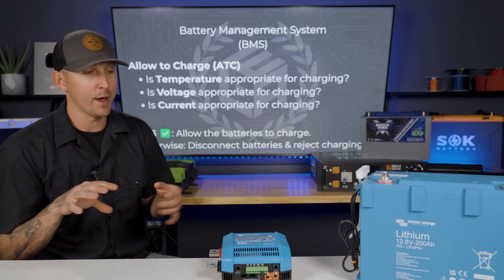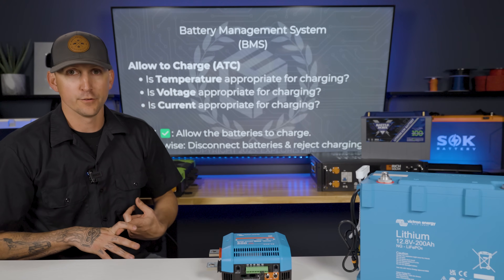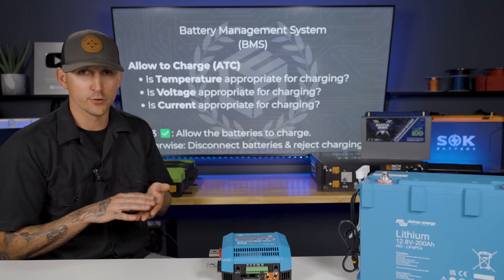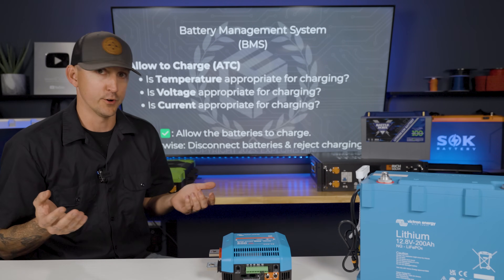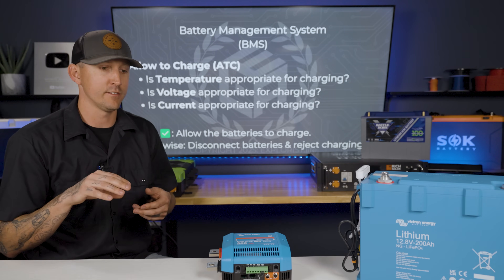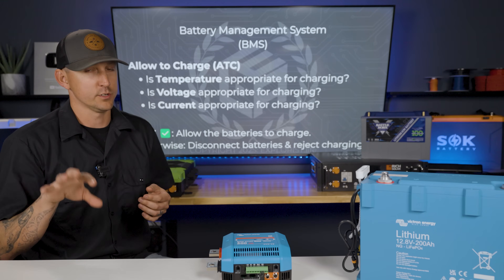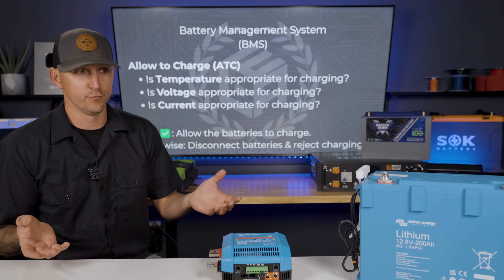The last way a battery can fall outside of allowable charge parameters is temperature. If the temperature falls too far below parameters, it's not going to charge. If it goes too high, it's not going to charge. A lithium battery in general — it depends on the manufacturer — but the batteries can typically be charged as long as they're above freezing, so above 32 degrees Fahrenheit. That's a general rule of thumb, though every manufacturer has its own tolerances.